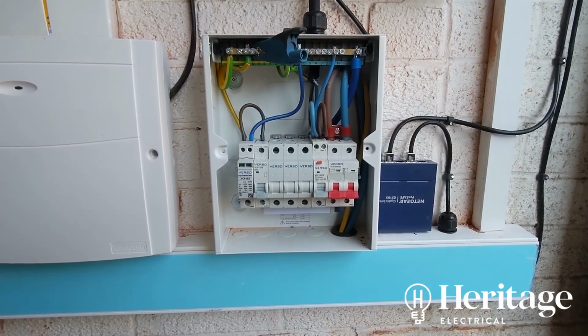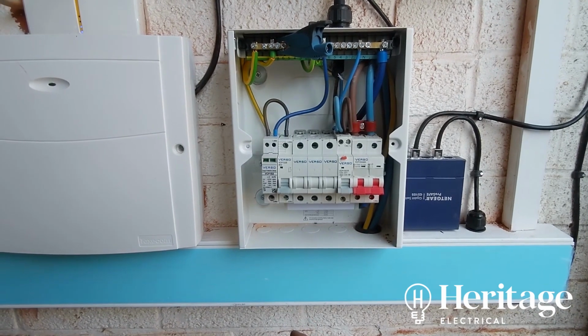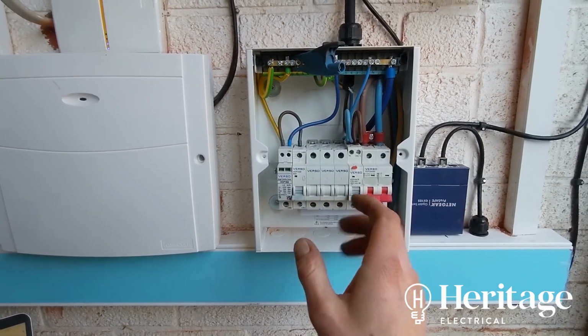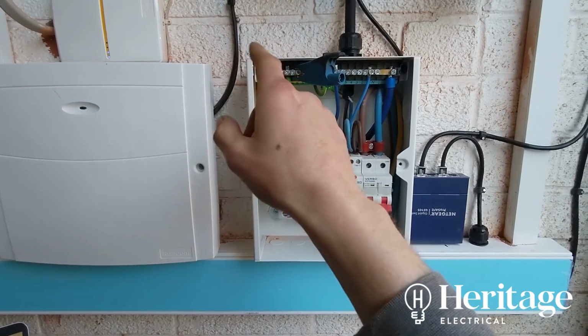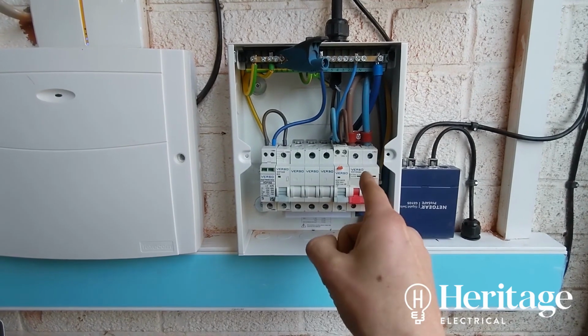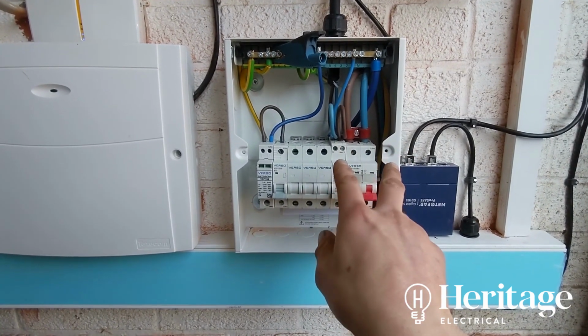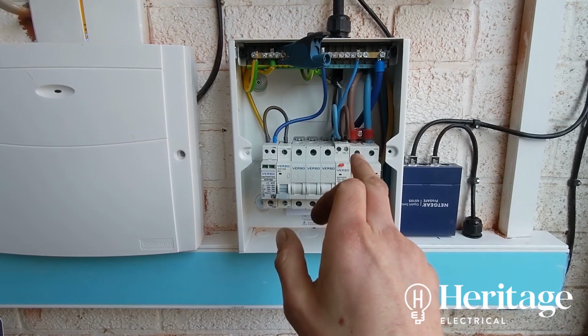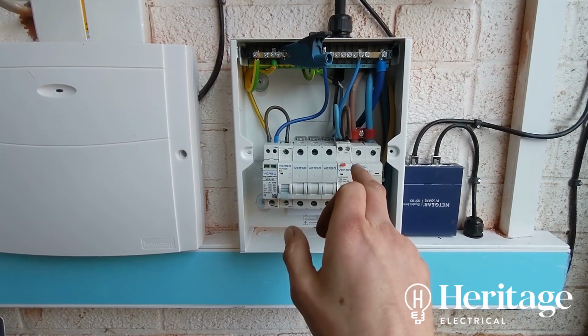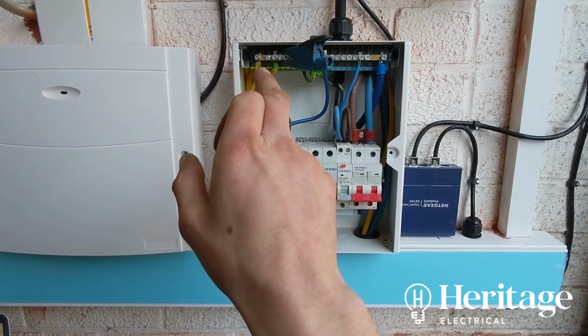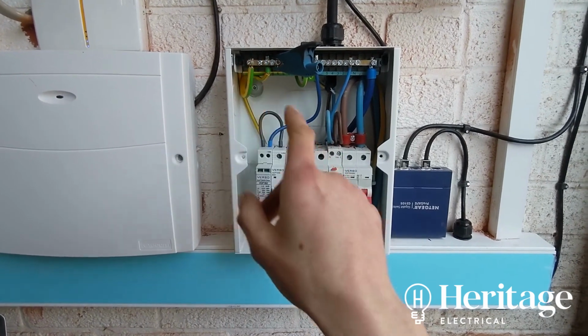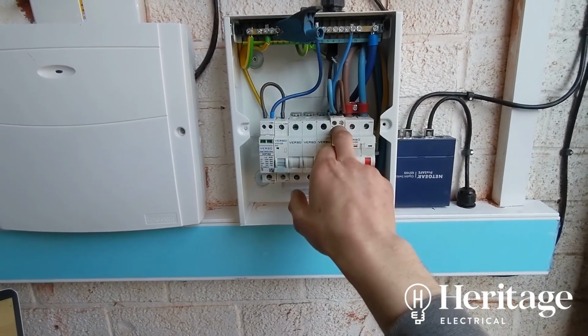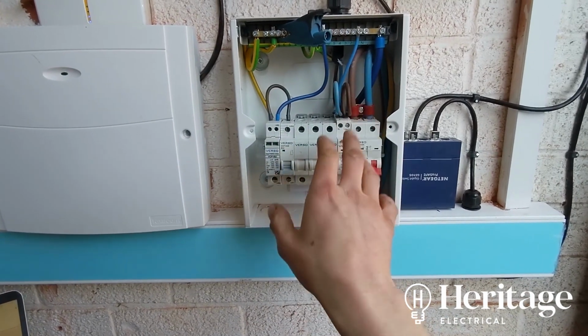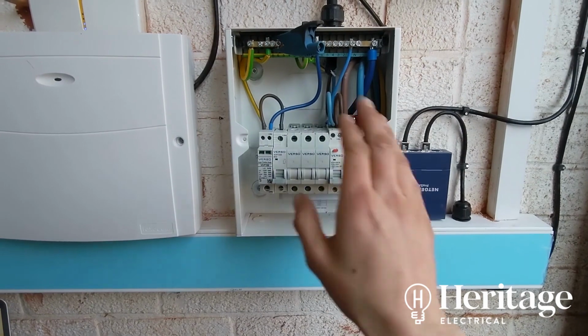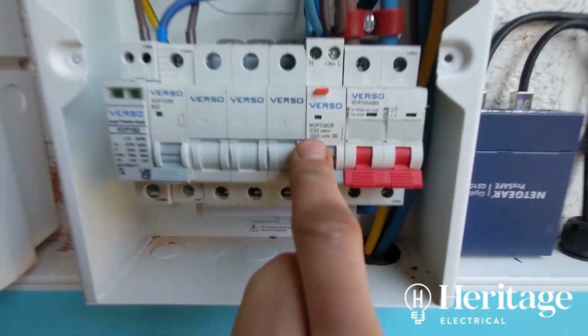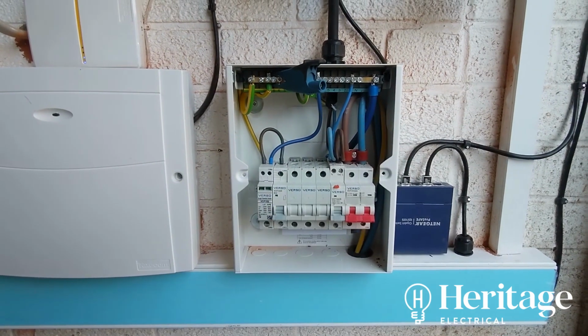It's a TNCS system, so the maximum value quoted by the DNO is 0.35, so we're just within that. We then reconnect that back up to the board, and we do a fault current measurement. So we do probe onto line and neutral, take one reading, and then a separate reading line to the earth bar. Sorry, brain fart there. And then we take the highest value just to make sure that the protective devices downstream are capable of interrupting super high fault currents, but in this case they're well within, you see, 6,000 amps. Fault current here is about 600.